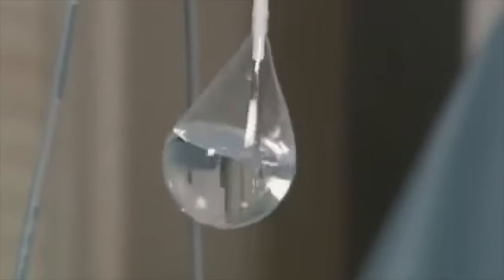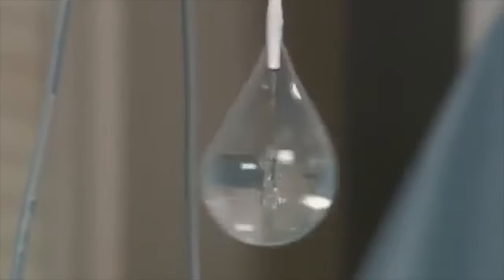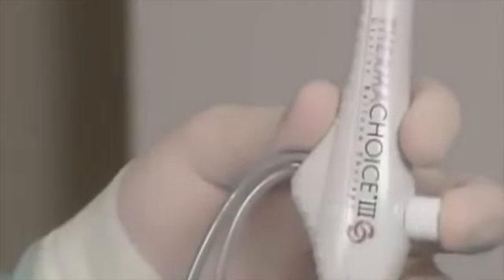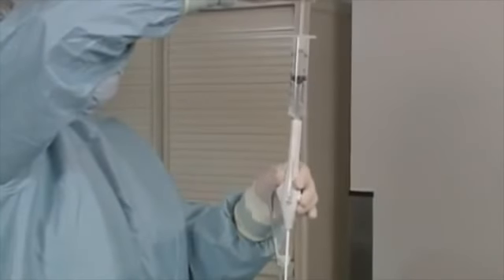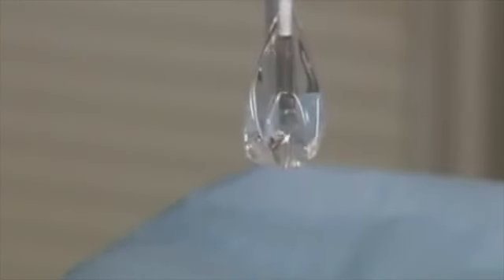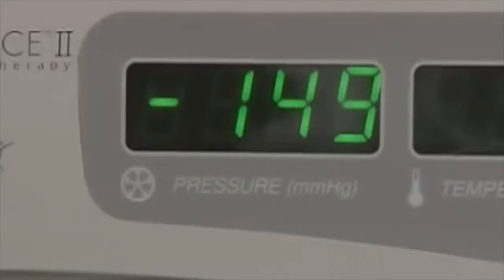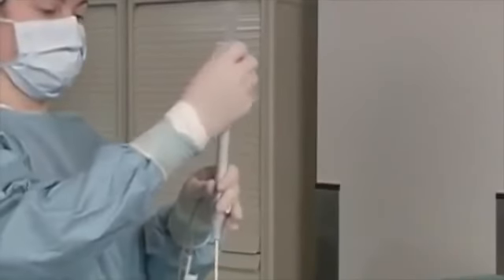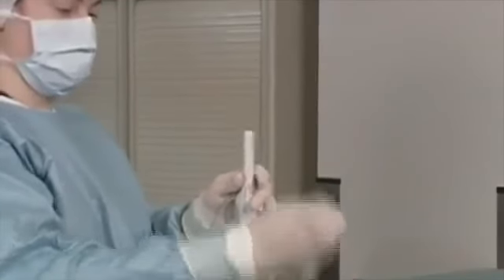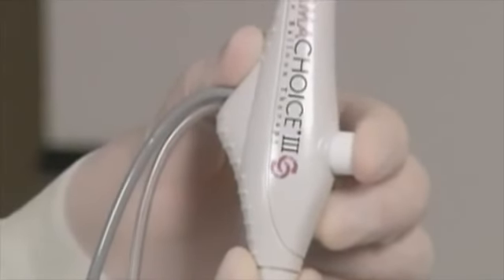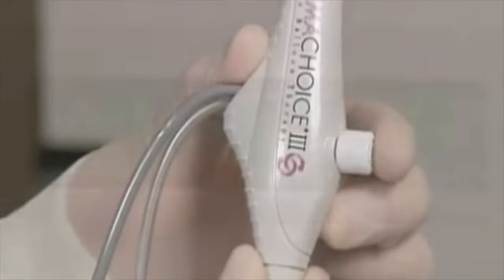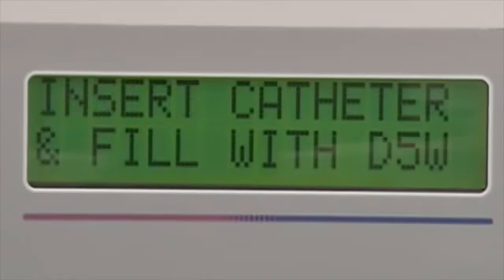When adding fluid during priming, ensure that the balloon fully opens so that none of its sides are touching. Once again, depress the trumpet valve, but this time slowly aspirate both fluid and air from the balloon until a negative pressure of -150 to -200 millimeters of mercury is reached, as indicated on the controller's pressure display. You may need to purge air from the syringe several times to attain the desired negative pressure. Note, never exceed -200 millimeters of mercury pressure. Now, release the trumpet valve to maintain a stable negative pressure for at least 10 seconds, after which you are ready to proceed with the next steps of the procedure.